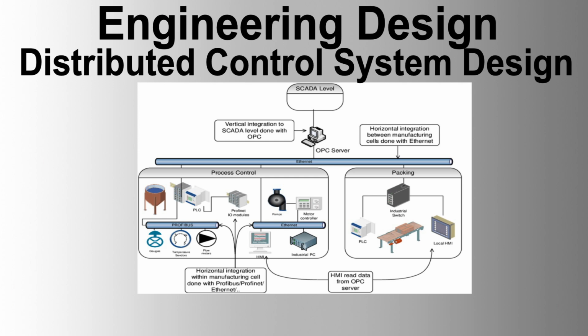The following systems must be connected to the DCS through dual redundant serial links: compressor UCP, generator UCPs, chlorination panel, diesel centrifuge package, LV switchboard, HVAC system, ESD F&G system, multiplexer panel, with a single serial link connection for vibration monitoring systems. Vendor must provide all necessary hardware for interface, while cables must be provided based on vendor specifications.